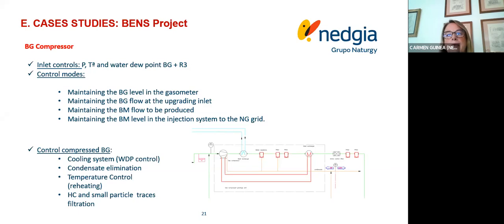Inside the compressor system, there is also control of the water dew point by means of condensating the remaining water content in the biogas. Therefore, reheating of the biogas is required, and after this, hydrocarbon and particle filtration is installed. The compressor includes a frequency converter that increases or decreases the motor speed in order to increase or decrease the discharge pressure and the flow of biogas.